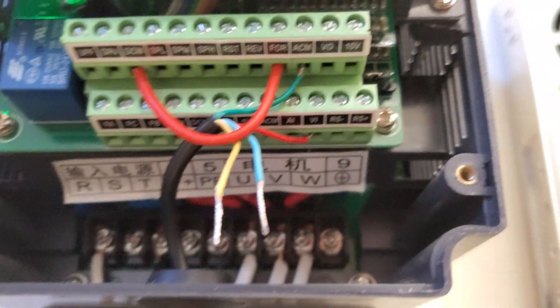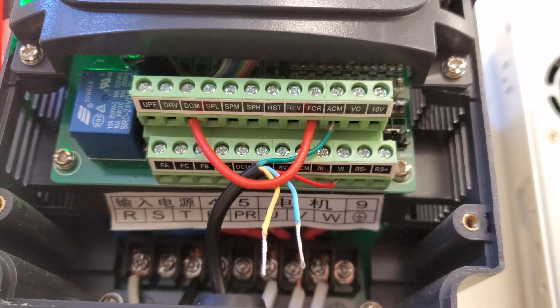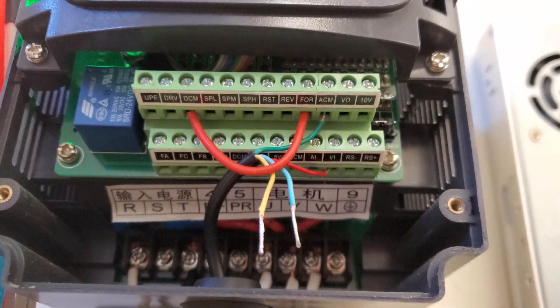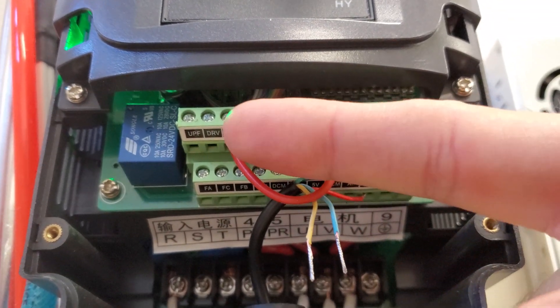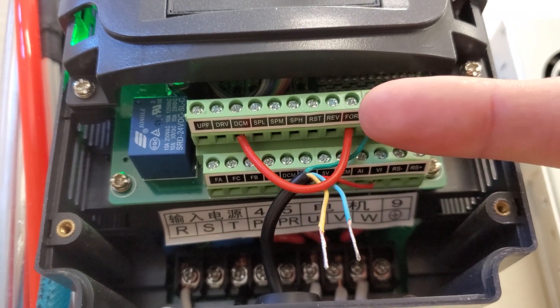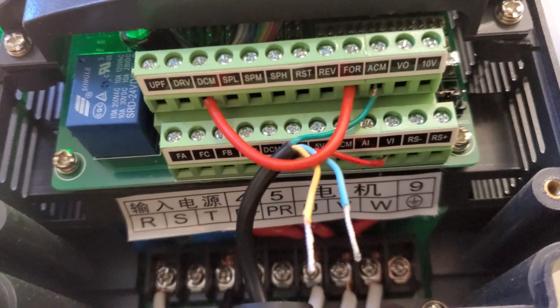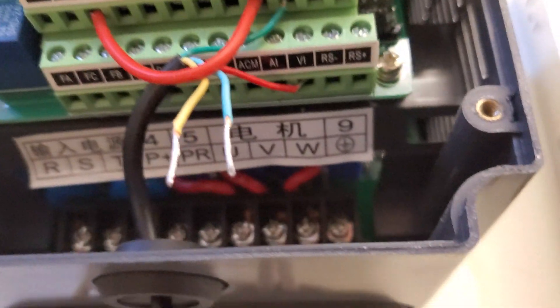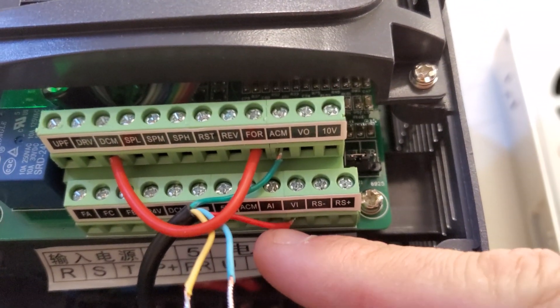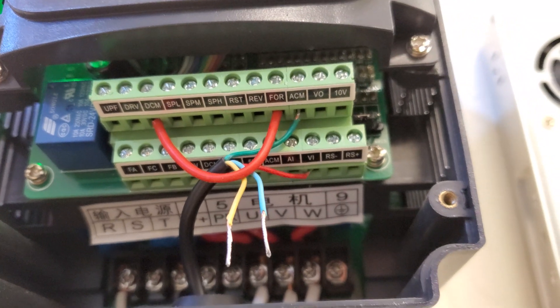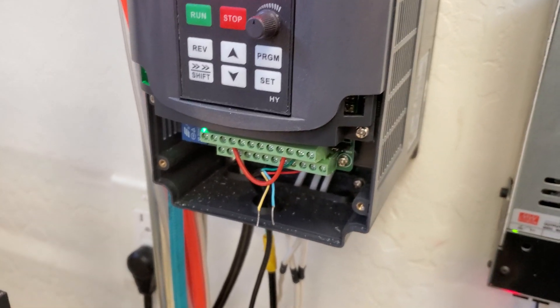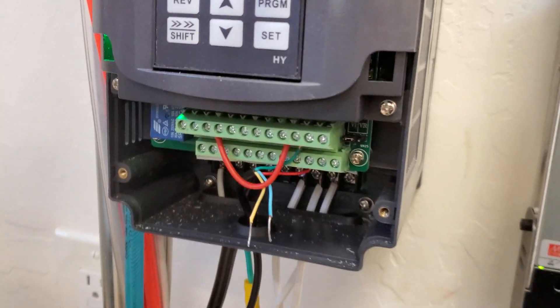First thing that you need to do is bridge the DCM and the forward, the FOR. You need to bridge those two together. So I just made a little jumper cable, touch those two together. The DCM is basically a common ground, and then forward is for the direction. And then the ACM line is considered a ground also, and then the VI down there with that red, small red wire going in. That is where the VFD is getting the information from the black box.